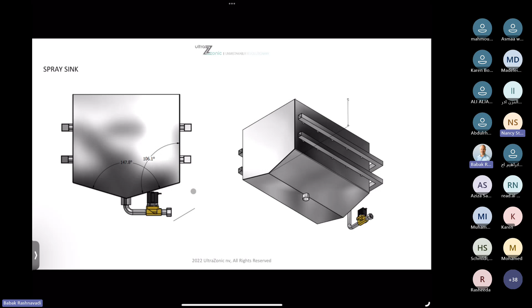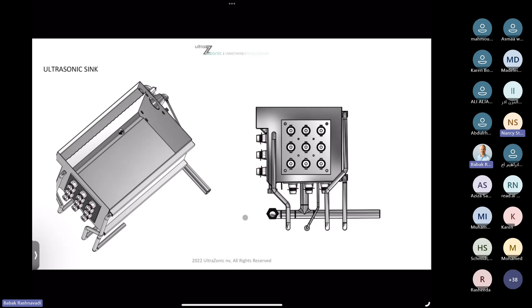And then here you have the ultrasonic sink. When you go further, you can see that we have a sink with transducers on 3 sides. We have 49 transducers on each ultrasonic device. Every tube we use is stainless steel. We don't do anything in plastics. We don't want to do anything cheaper because this always gives trouble with maintenance and the durability of your ultrasonic sink. Can you go to the next slide?